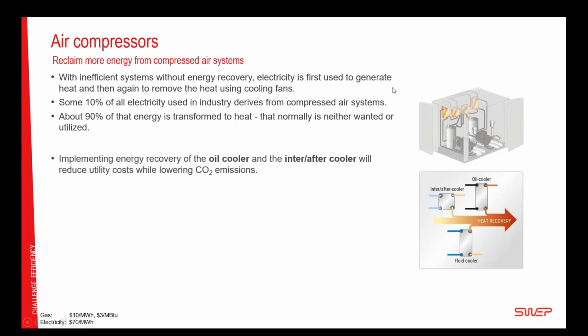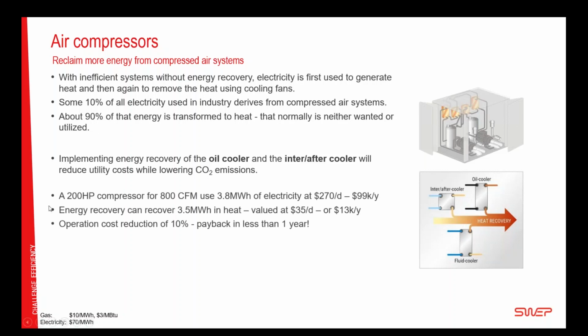But if an oil cooler, intercooler, and fluid cooler are introduced, it's possible to recover most of this energy. So in an example here, a 200 horsepower compressor makes about 800 CFM, cubic feet per minute. That is a fairly large but still standard size industrial compressor. It's something you can still buy from the catalogs, so to say. It will use about 3.8 megawatt hours of electricity per day, which means $270 per day, or $99,000 per year, 24/7, 365. Since this process is so inefficient, we can recover almost all, or 3.5 out of 3.8 megawatt hours, of the heat. Since it's heat and not electricity, the value is less. So it's only about $35 per day, but it's still $13,000 per year.